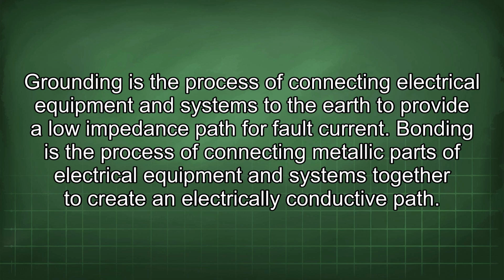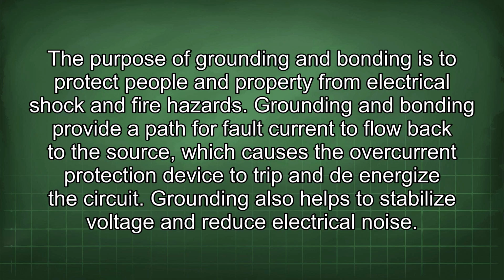Grounding is the process of connecting electrical equipment and systems to the earth to provide a low impedance path for fault current. Bonding is the process of connecting metallic parts of electrical equipment and systems together to create an electrically conductive path. The purpose of grounding and bonding is to protect people and property from electrical shock and fire hazards. Grounding and bonding provide a path for fault current to flow back to the source, which causes the overcurrent protection device to trip and de-energize the circuit. Grounding also helps to stabilize voltage and reduce electrical noise.